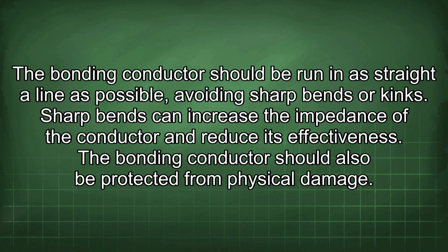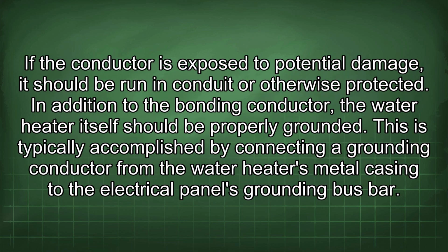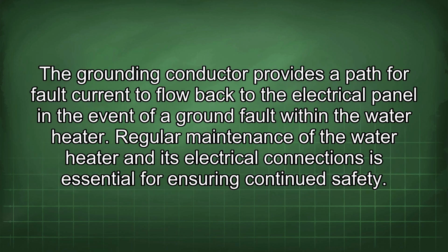The bonding conductor should also be protected from physical damage. If the conductor is exposed to potential damage, it should be run in conduit or otherwise protected. In addition to the bonding conductor, the water heater itself should be properly grounded. This is typically accomplished by connecting a grounding conductor from the water heater's metal casing to the electrical panel's grounding bus bar. The grounding conductor provides a path for fault current to flow back to the electrical panel in the event of a ground fault within the water heater.